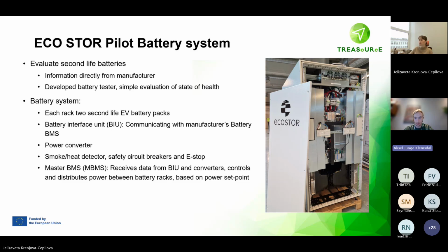The battery system, shown in the picture on the right, is one rack, and each rack consists of 2 second-life EV batteries. These racks can be grouped together into a whole system. We developed what we call a battery interface unit, which communicates with the manufacturer's BMS and gets out all the cell voltages, temperatures, battery faults, and other data. There's a power converter which converts DC power in the battery to AC in the building, plus a smoke and heat detector, safety circuit breakers, and an e-stop for safety.